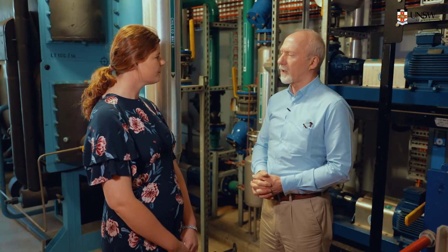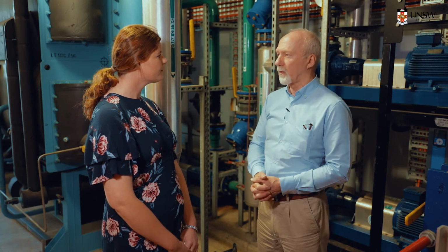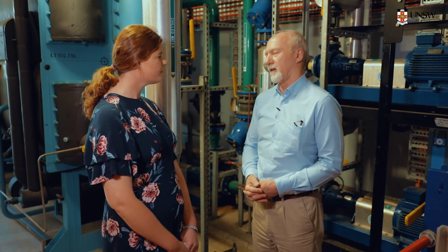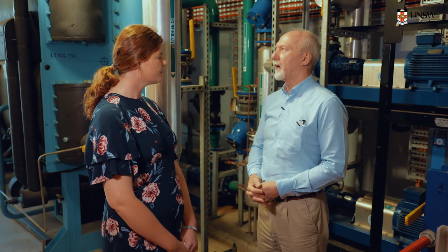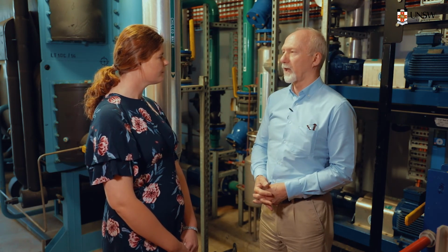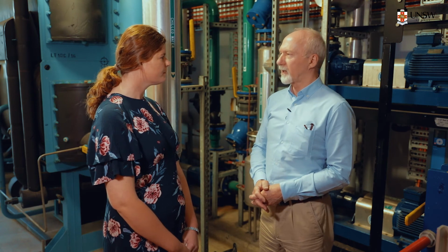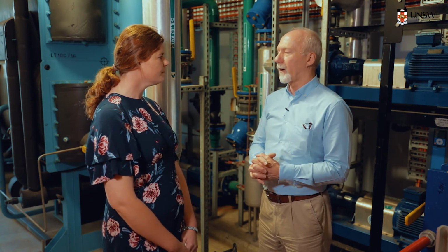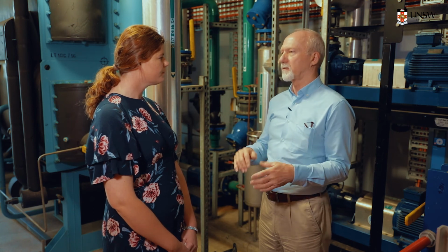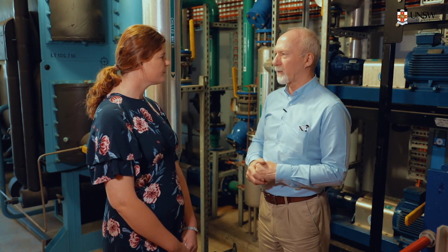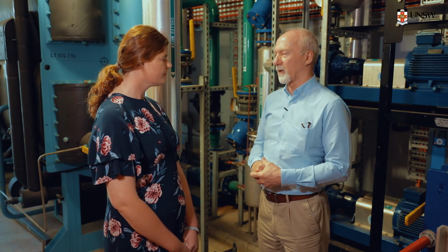At the moment I'm running the generator at 700 kilowatts, slightly derated in deference to extending its life. That means the absorption chiller is running at a maximum of 200 kilowatts. We also have capacity to put heating into the system to supplement the HVAC installation, up to a maximum of 460 kilowatts. The amount that goes into either heating or cooling is split, so if I'm using 50% of my cooling capacity, I can only use 50% of my heating capacity, and so on.